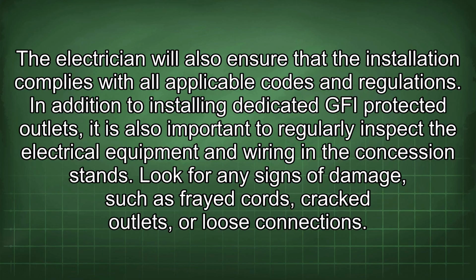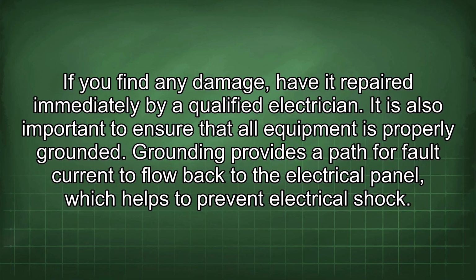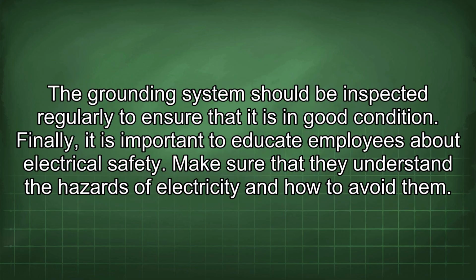In addition to installing dedicated GFI protected outlets, it is also important to regularly inspect the electrical equipment and wiring in the concession stands. Look for any signs of damage, such as frayed cords, cracked outlets, or loose connections. If you find any damage, have it repaired immediately by a qualified electrician. It is also important to ensure that all equipment is properly grounded. Grounding provides a path for fault current to flow back to the electrical panel, which helps to prevent electrical shock. The grounding system should be inspected regularly to ensure that it is in good condition.